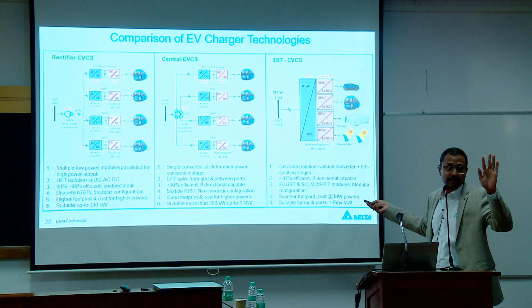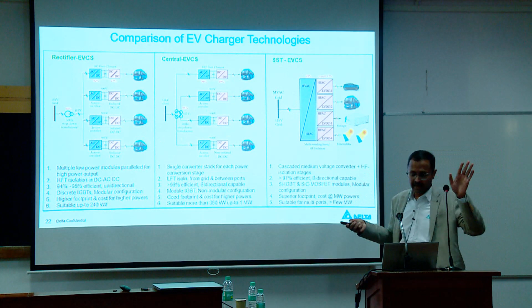However, this is the future, because there is a clear disconnection from the AC grid to your outputs, since both sides are active. So any fluctuations on this side do not influence the other. If you have storage on this side, you can even run on the microgrid. That's the beauty. But we don't have permission today to connect a solid state transformer to the grid, because of the protection point of view. The norm still has to come from our regulatory authorities.